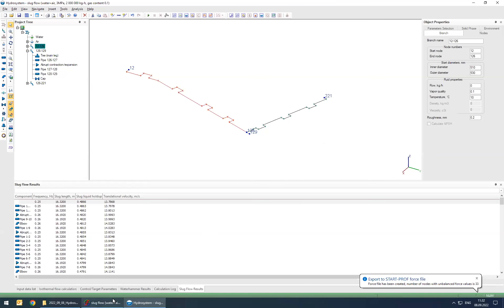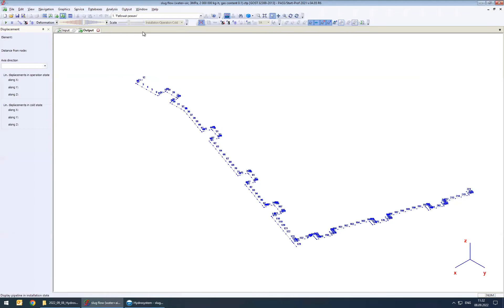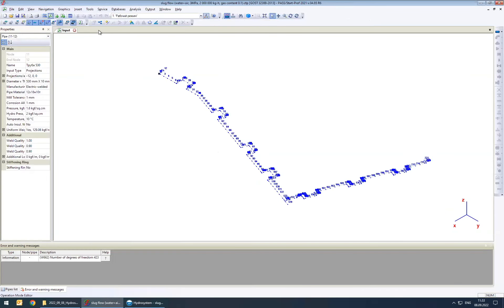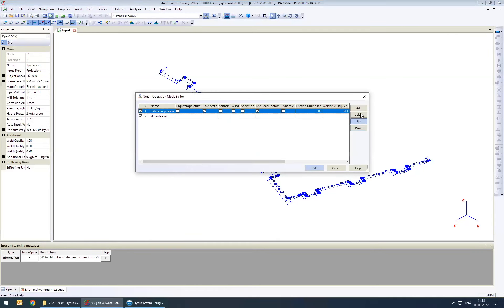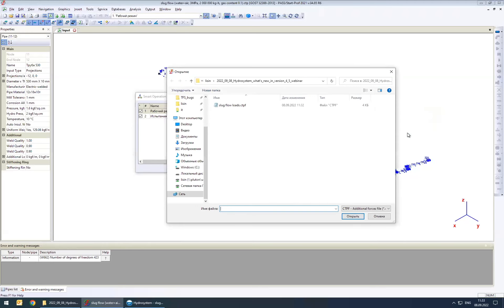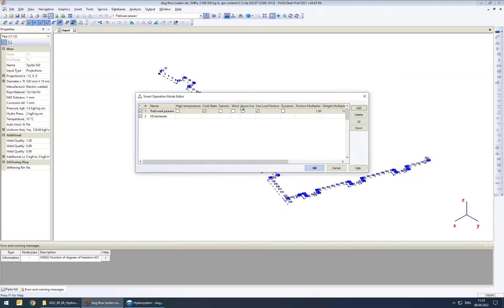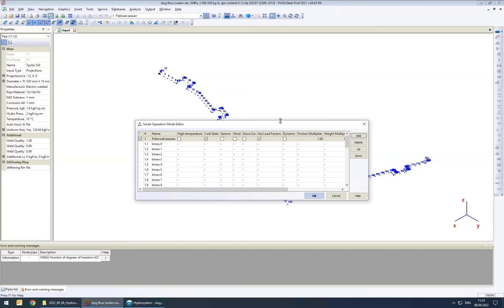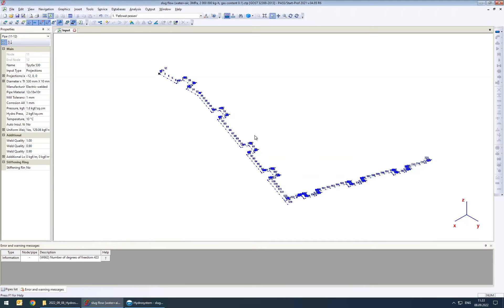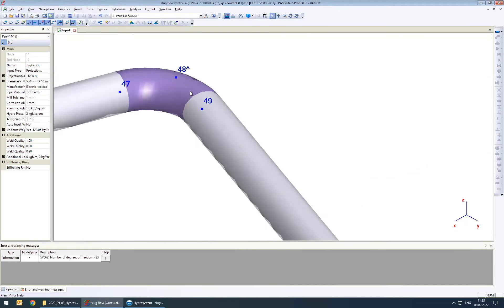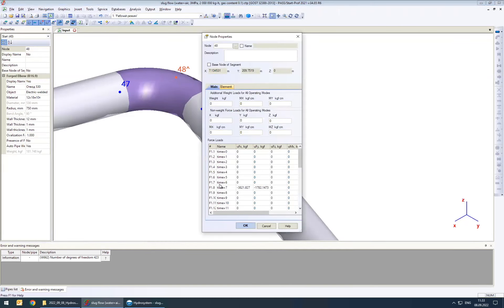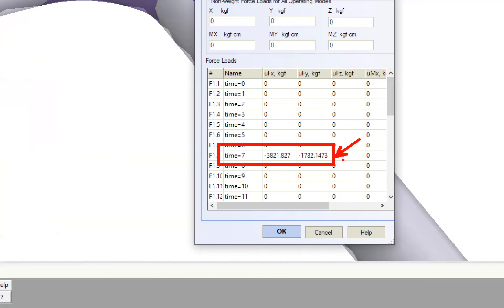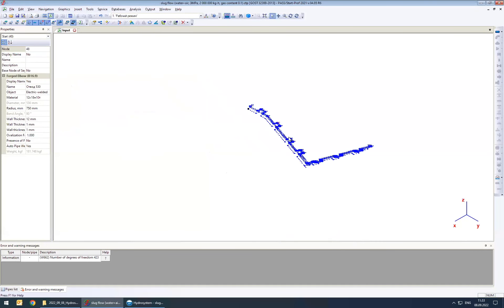After exporting, we go back to Start-Prof. In Start-Prof, you go to Working Modes / Operation Modes and select 'Load force loads from file.' You select the file, and a different operation mode is created for each node — because you need to calculate all these loads separately from each other. After pressing OK, for every node that has these additional loads, you will see a special symbol. By clicking that node, you can see the forces and their coordinates — everything you need to perform stress analysis.